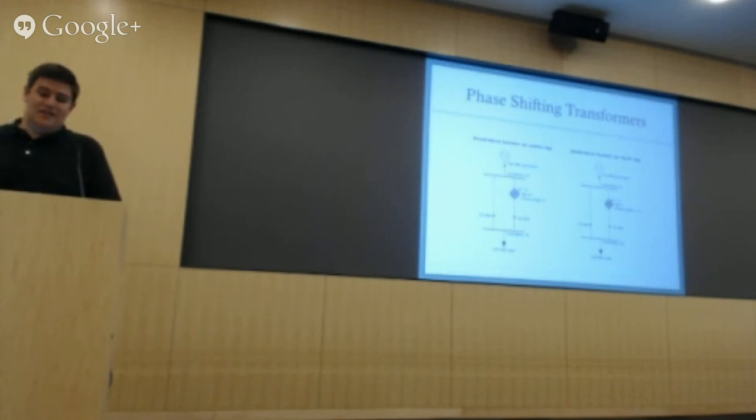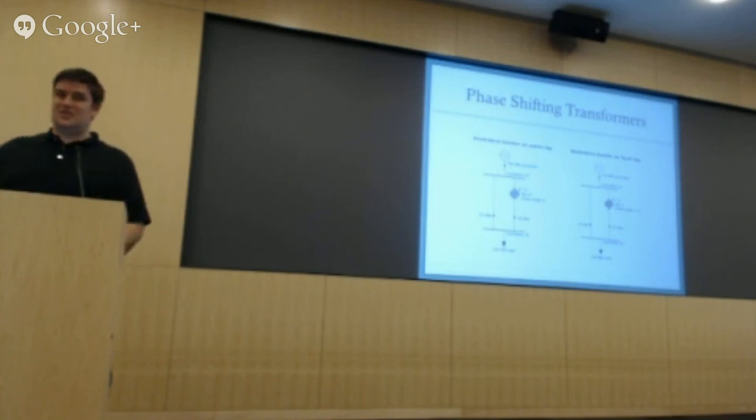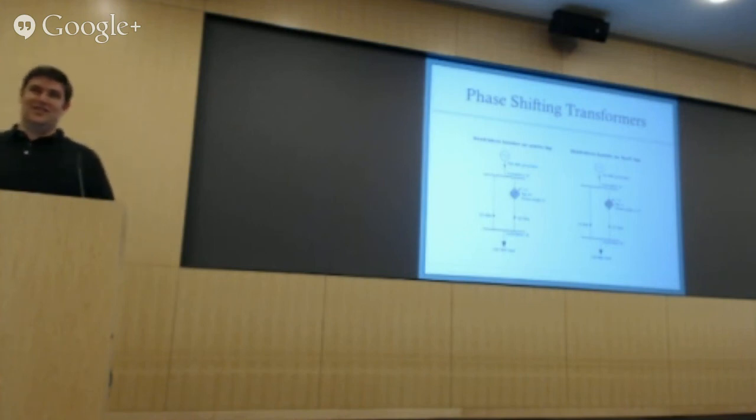But when you're a customer, not typically for residential, but for commercial, you have to have power factor correction, or you have to manage your power factor, because if you lag too much, the utility charges you. You're essentially drawing more current than you're giving back at every half cycle, and you're heating up the lines more, and you're not actually producing usable work from that.